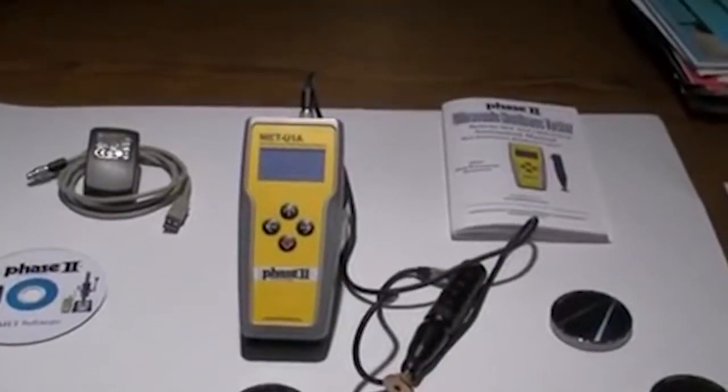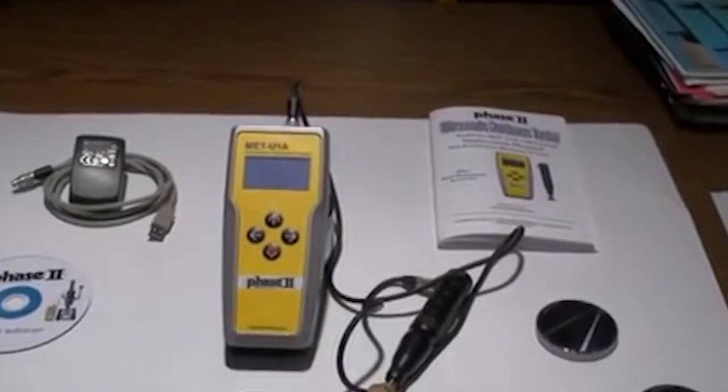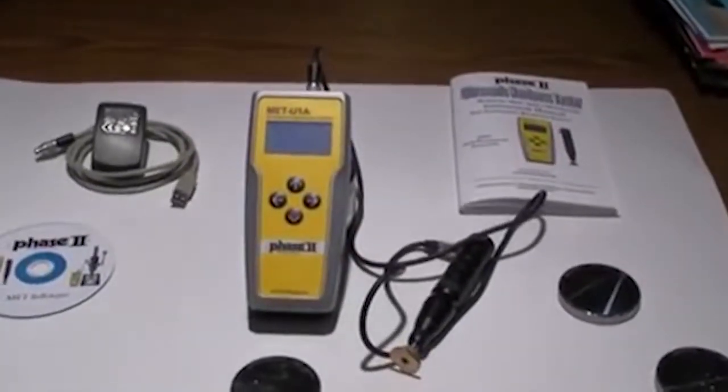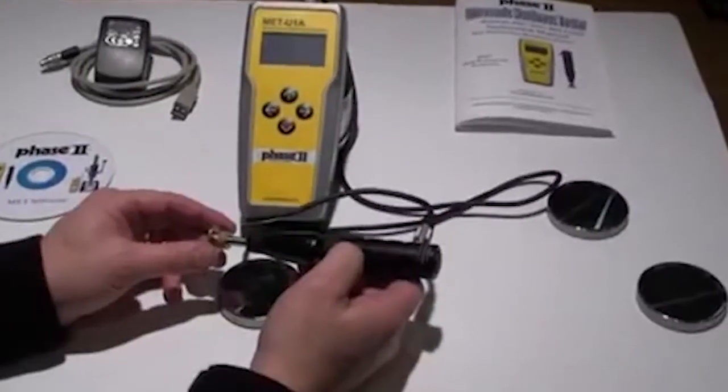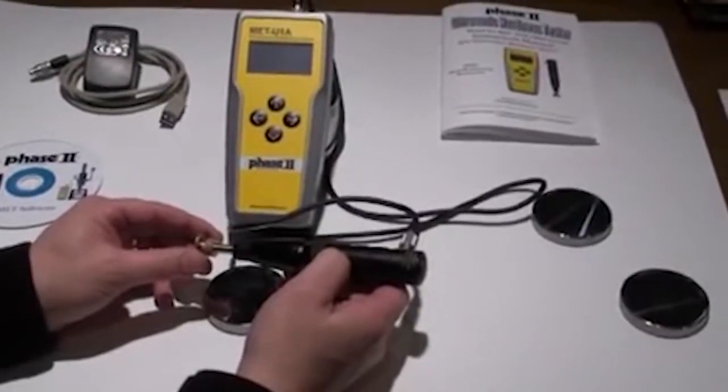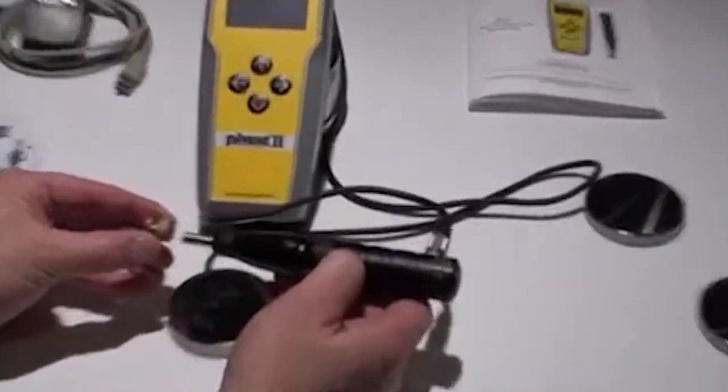This will take a few minutes of practice to get the load force correct without any vibration. The brass foot can be removed if necessary to take tests in tighter areas.